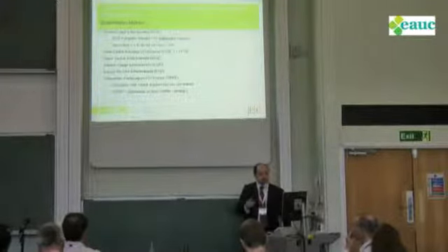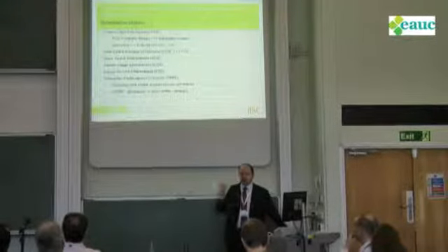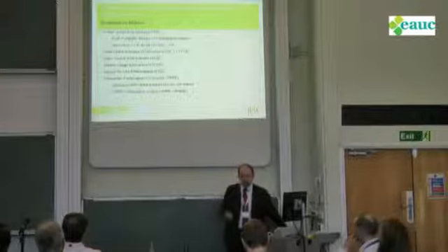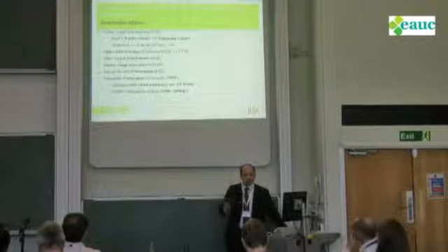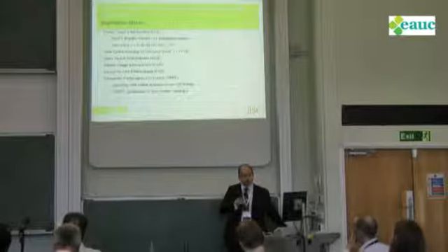Data center infrastructure efficiency, that's basically 1 over PUE. Some people like to look at it as, my data center is X% efficient. So that's just a different way of looking at it. There are lots of other new metrics that have just come out recently from the Green Grid. A lot of these are from the Green Grid actually.